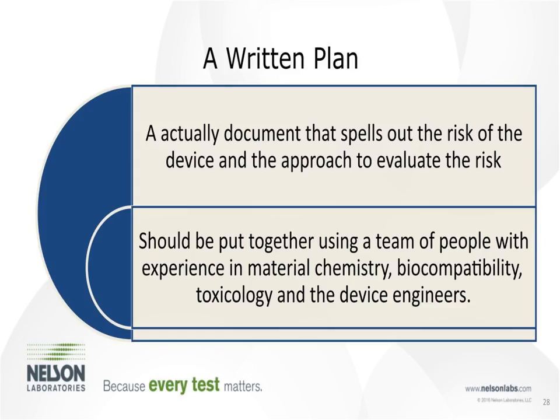I do want to emphasize that this is a written plan. You can't just go to the FDA and say, we evaluated risks, these are the tests we felt like we had to do, and we did them and passed, and we're good. You really have to sit down, think through that risk, those materials, all the things we talked about, and put it on a paper plan, a document that spells out what the risks are, how you're going to address those risks, and have a signed conclusion that this is how we're going to approach our biocompatibility with this device, and have those people involved, those chemists, those biocompatibility experts, the toxicologists.